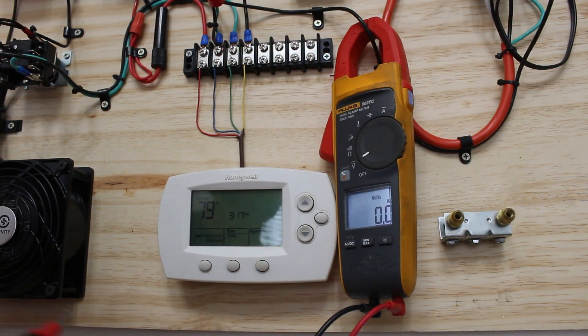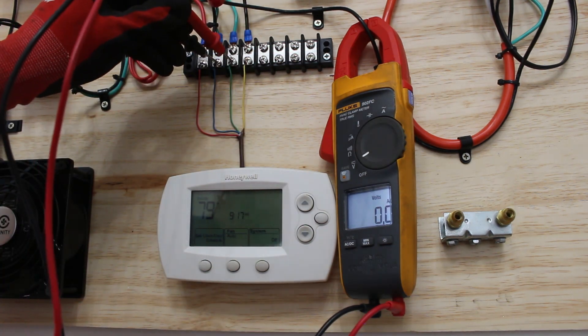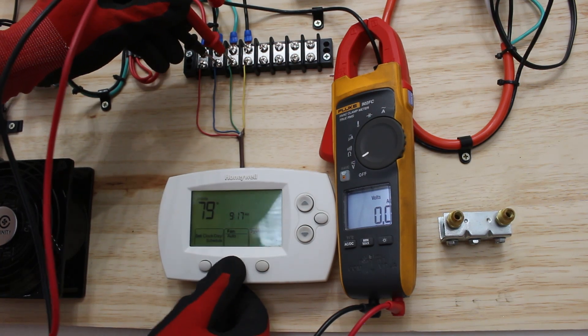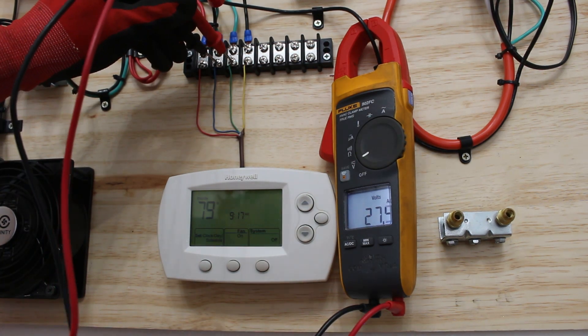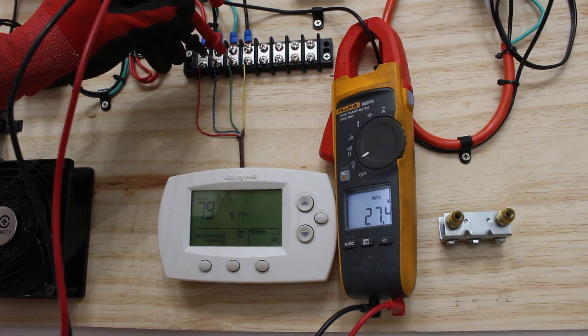Let's start with G, our fan. So we're going to go from common to G, C to G. System is off, we have zero volts, and if we put it on, now we have 28 volts, now power sending through.